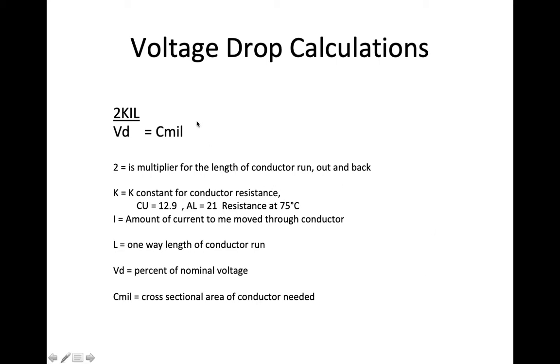Looking at the formula, 2 is the multiplier for the length of the conductor run, out and back. So I'm going to measure the distance one way, out, but this 2 is going to take care of the additional run coming back. K is the K constant for the conductor. Copper K constant is going to be 12.9. Aluminum is going to be 21. And this is at 75 degrees C.